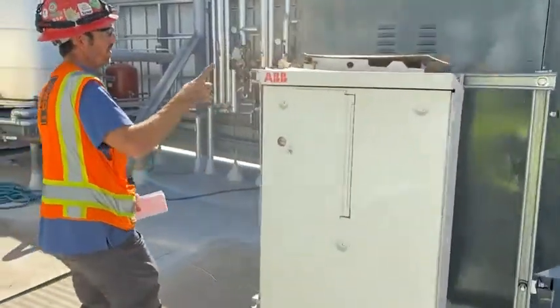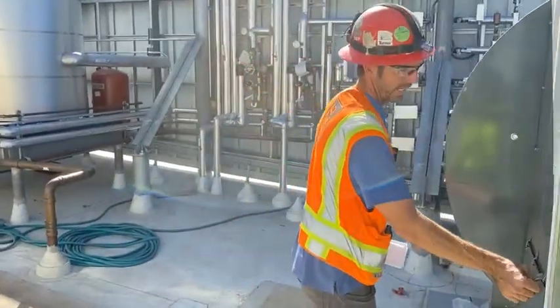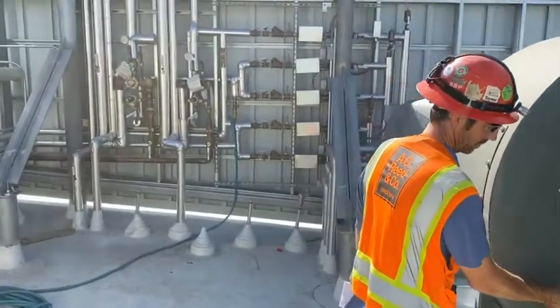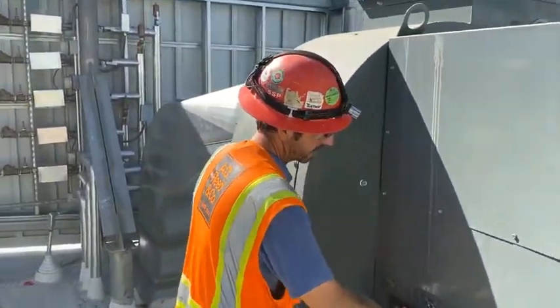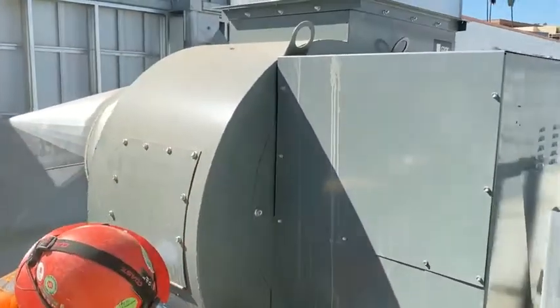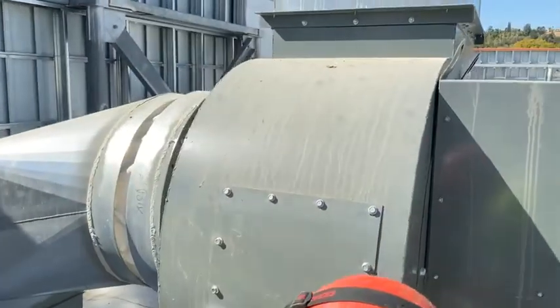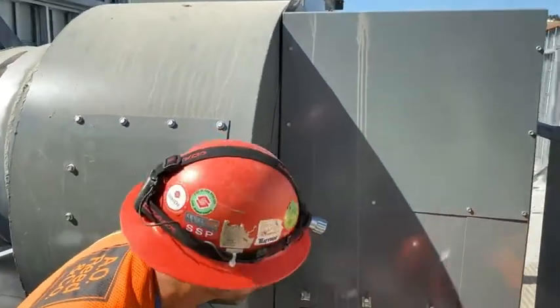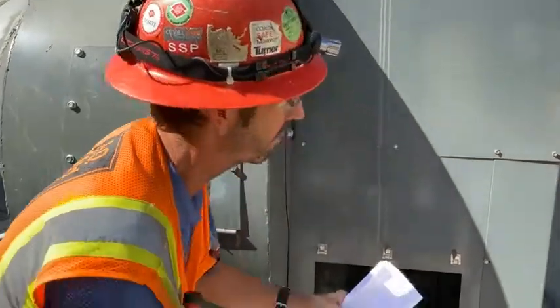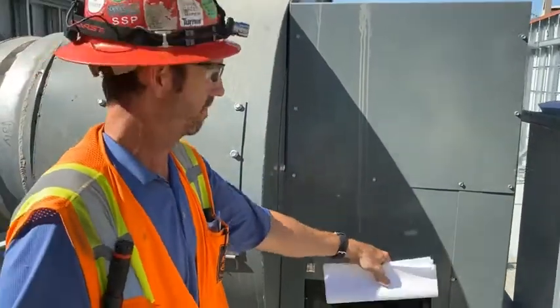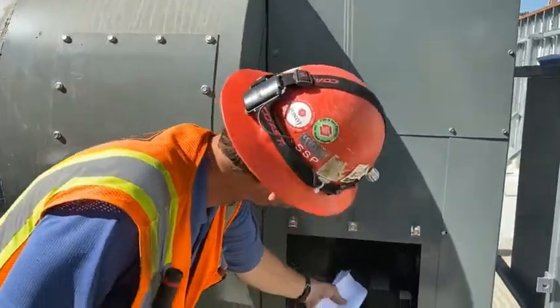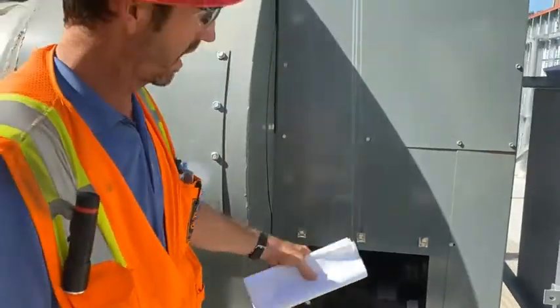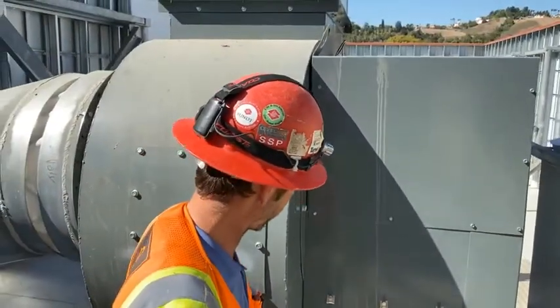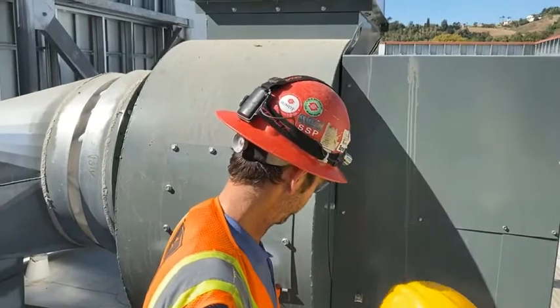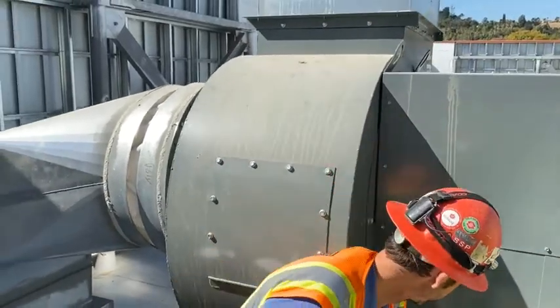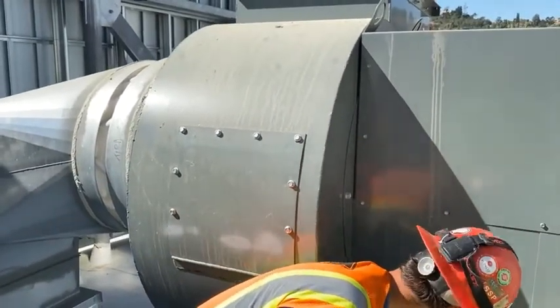So this is a centrifugal utility fan. It's belt driven. This is an access port to look at the belts. Again, anytime you would touch the belts or do any type of belt tensioning, you'd want to turn off the unit, lock out, tag out, power to the unit, okay? So these are inspection doors for the motor and the belts. There's dual belts on this unit right here. Adjusting the tension of the belts is done with this plate right here.